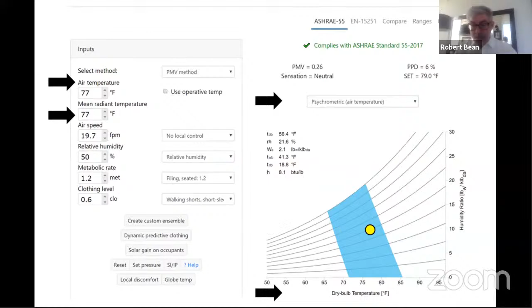So we have to do an assessment for exterior zones and those zones that have a high solar load, because they will be directly influenced by the sun, the shortwave radiation, which has an influence on the mean radiant temperature. So very rarely will you see these two numbers equal at the exterior, but you'll see them more similar when we get more towards the interior of the spaces. So we can calculate the mean radiant temperature, and we specify what the air temperature is based on our control points.